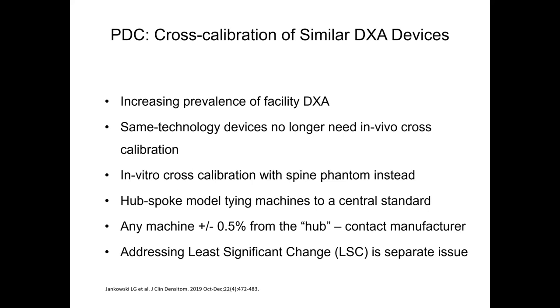We recommend that when machines are similar, you use an in vitro technique that uses phantom spine calibration, a hub and spoke model with machines being tied to the calibration of a central machine. After going through the process, if any machine is plus or minus 0.5% deviating from the hub machine, your representatives from manufacturers should be contacted to adjust the calibrations of the machines.